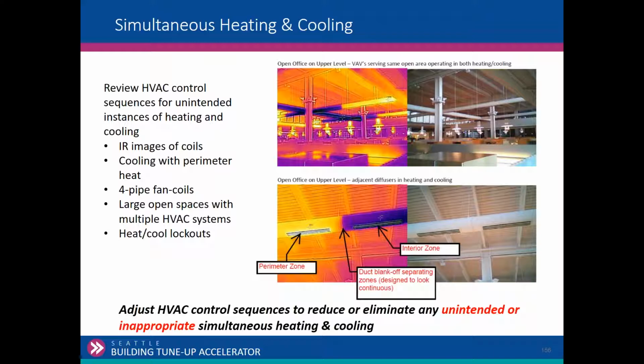Simultaneous heating and cooling, you know, the boiler and chiller being enabled at the same time, that's always one. I received this photograph from an engineer a while back. This is a VAV system, which is actually designed to be heating and cooling. And it's something at the code level we've been trying to figure out how to deal with, VAV systems.